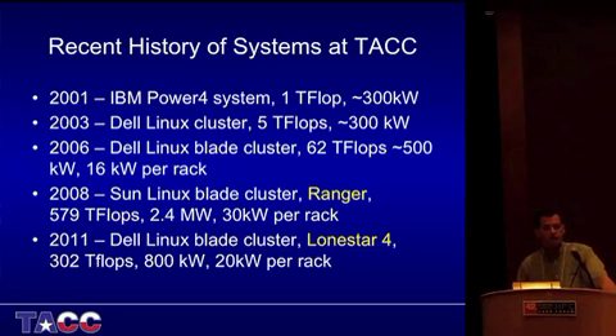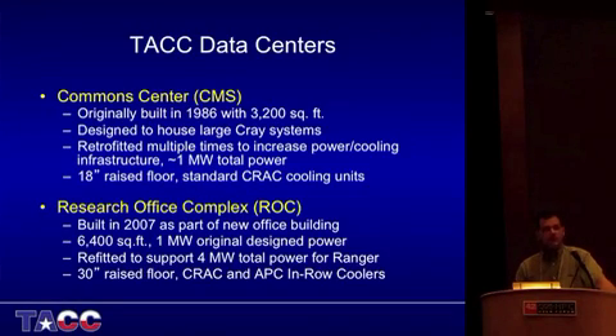Finally, earlier this year we deployed Lone Star 4, our fourth incarnation of Lone Star. It's 302 teraflops, 800 kilowatts of total compute power, about 20 kilowatts per rack. Again we had to make a design decision here: we actually left space in the racks just to keep the power in the rack low enough for our current data center.